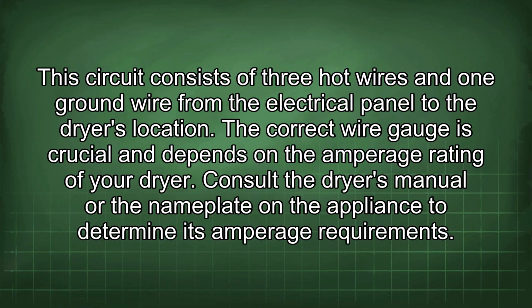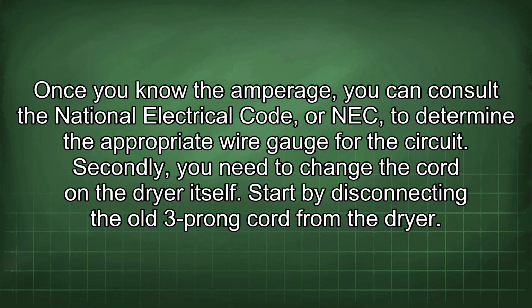The correct wire gauge is crucial and depends on the amperage rating of your dryer. Consult the dryer's manual or the nameplate on the appliance to determine its amperage requirements. Once you know the amperage, you can consult the National Electrical Code, or NEC, to determine the appropriate wire gauge for the circuit. Secondly, you need to change the cord on the dryer itself.